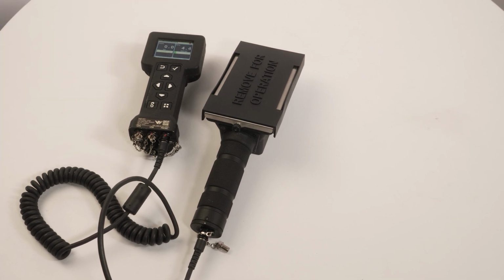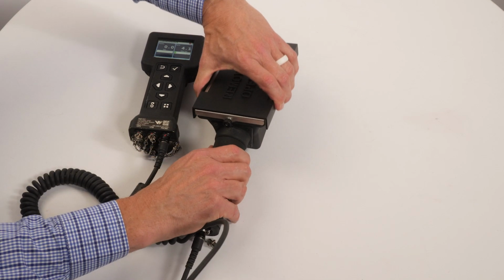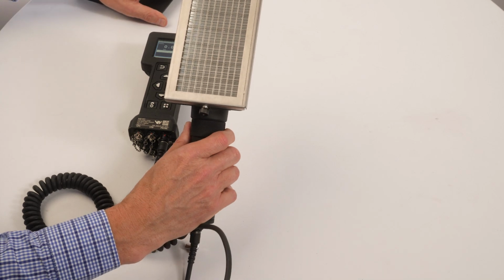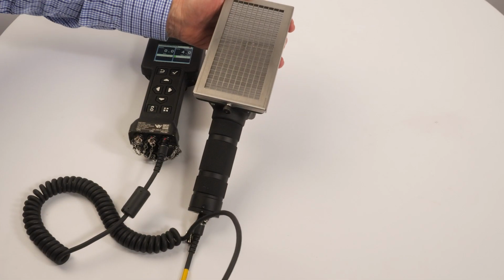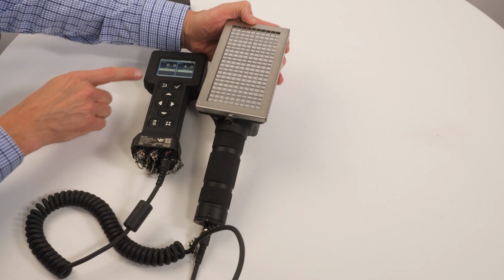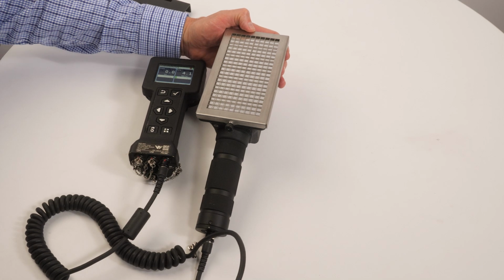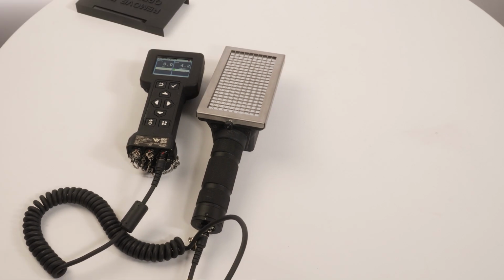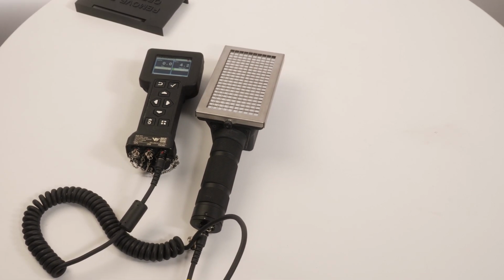If the increase in counts is caused by a light leak, the elevated reading you saw when facing the light source will lower slowly. If you remove the opaque material and turn the probe face towards a light source again, those counts should increase. If a light leak is present, the alpha and beta count rates will rise abnormally high again. If you determine there is a light leak, follow the troubleshooting steps in the manual based on your observations.